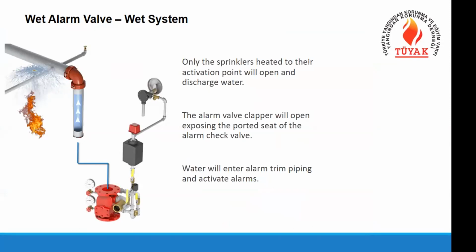Okay, this is basically a wet alarm valve by the name. You can see it works as an alarm device. It gives an alarm. Here you have a water motor alarm. It's like a gong. It turns with the water velocity and it gives an alarm mechanically, and it's ringing like a bell. So it gives a mechanical alarm to the building, to the people in the building to escape, and also for the fire brigade to approach the right place for the fire.